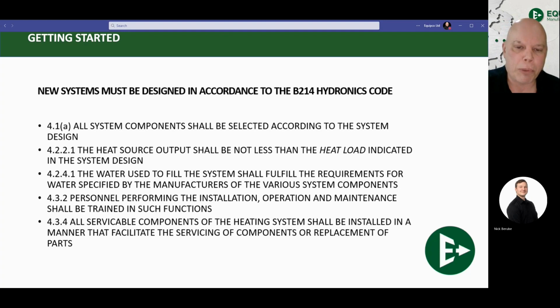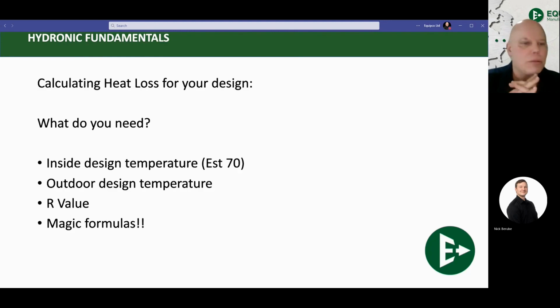434. All serviceable components of the heating system shall be installed in a manner that they can be serviced or replaced. What does that mean? Ball valves and unions are your best friends in hydronic systems. We should be able to put this together. We should also be able to take it apart because we need to be able to get access to our heat exchangers, get access to our air separators, clean these things, clean our mixing valves. That's part of the process of a hydronic system, the maintenance of it. It is not a set it and forget it. We do need to get into these systems and clean them up every now and again.